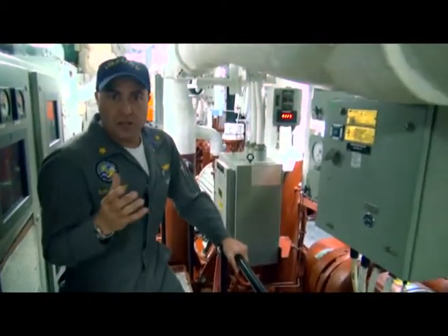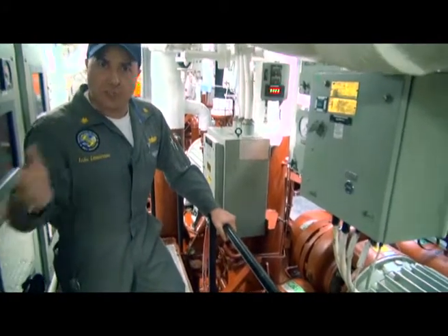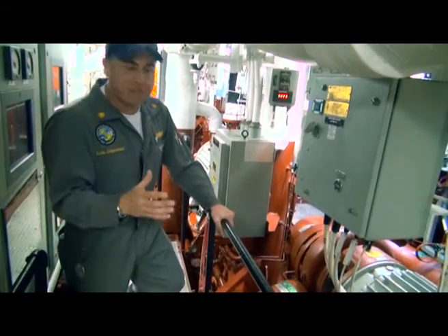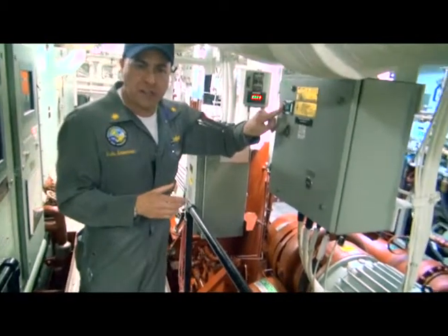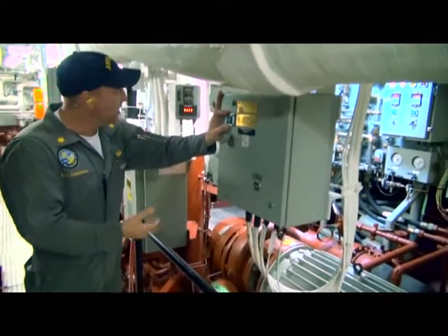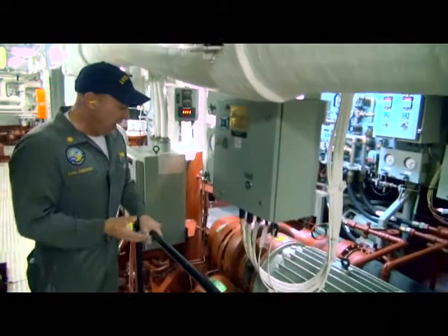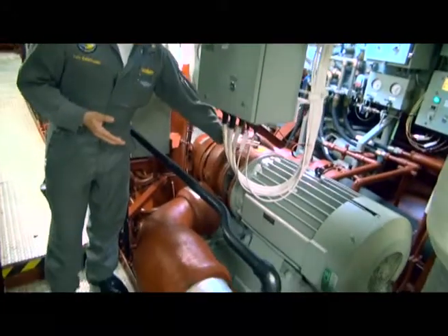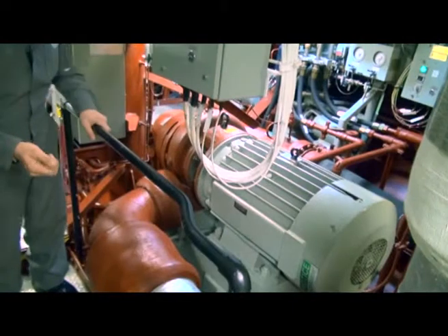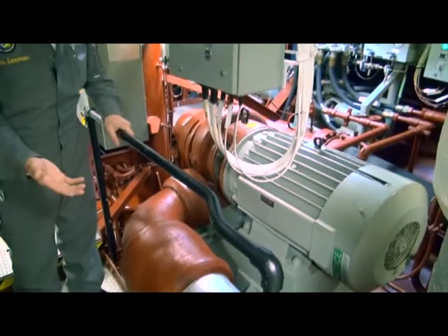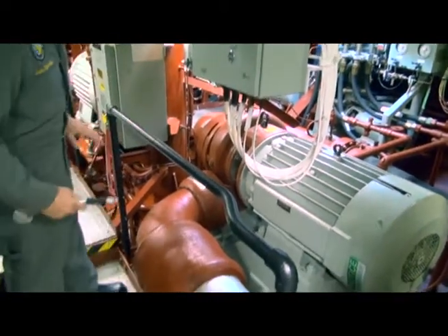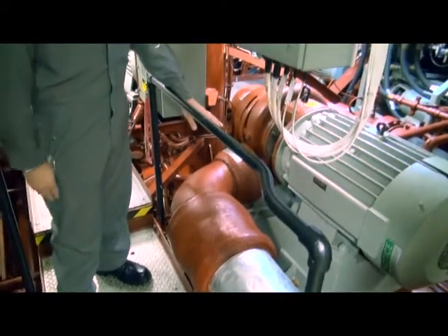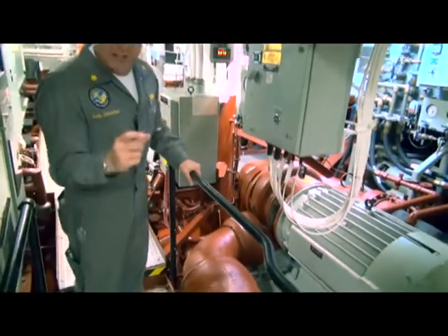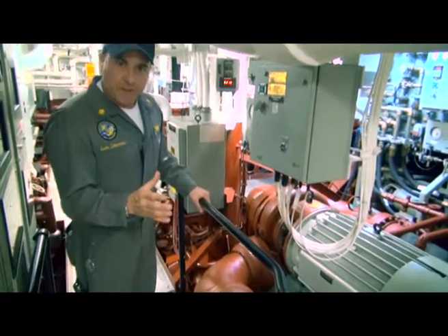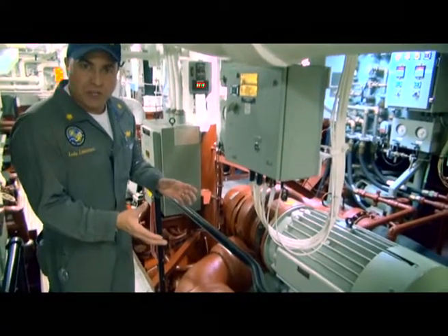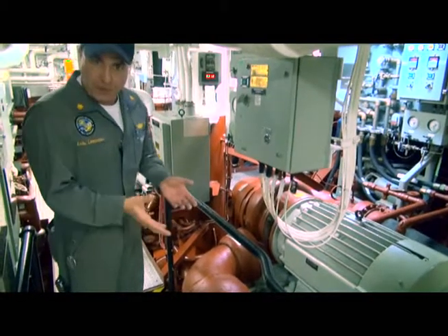For all these material conditions, we check our interlocks, we check our valve indications at each location. Obviously, things like pump running lights, we want to make sure that those work when the pump's running and that they secure when the pump's off. We're going to check for proper rotation. We're also going to check when we secure the pump for reverse rotation, to make sure that the check valve's not leaking by. In this case, on this ship, a DDG, the check valve does not have an indicator. So we like to try and check for some check valve slamming or some check valve noise, to make sure that it's seating properly. That's another thing we like to look for.